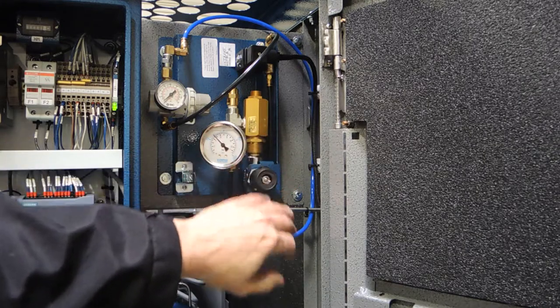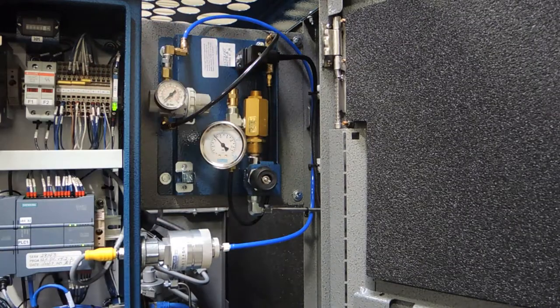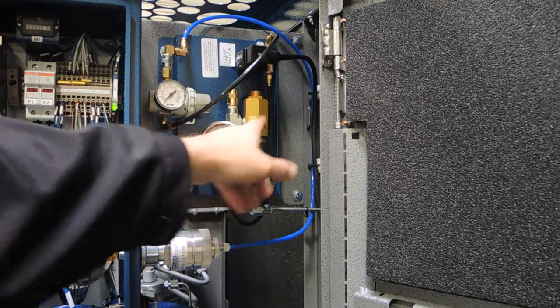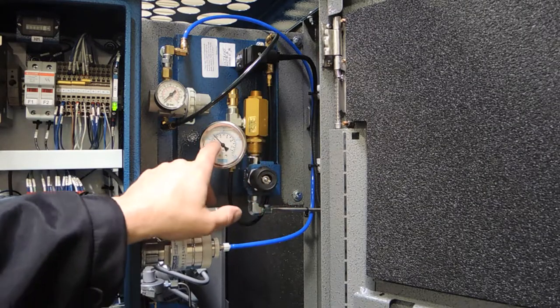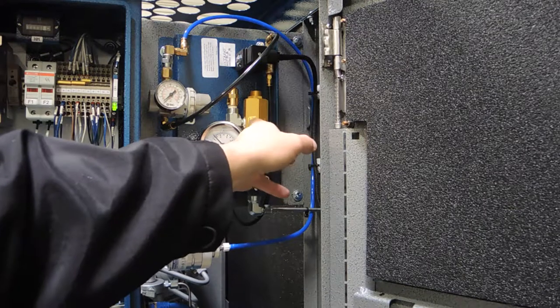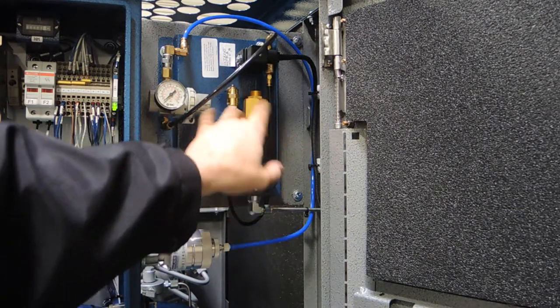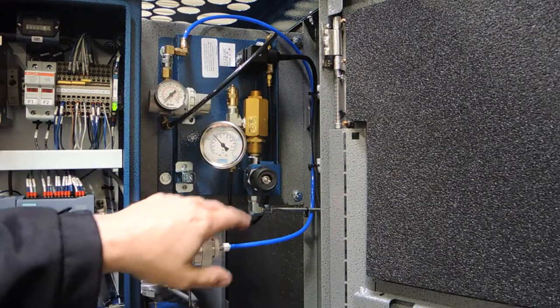This is more of a maintenance valve. If you had to work on the system, you can turn off your high pressure air there to do any work on the system. It's actually got a low pressure regulator. We're taking the 6,000 psi and bringing it down to about 65-70 psi through this low pressure adjustable regulator, which also has a relief valve on it. If the regulator goes bad, the relief valve will pop off and protect the rest of the system.